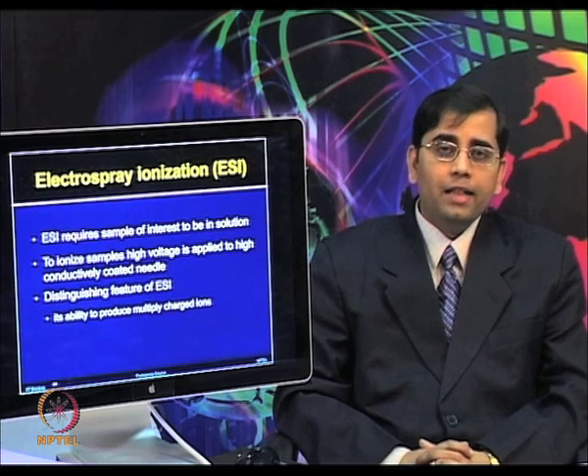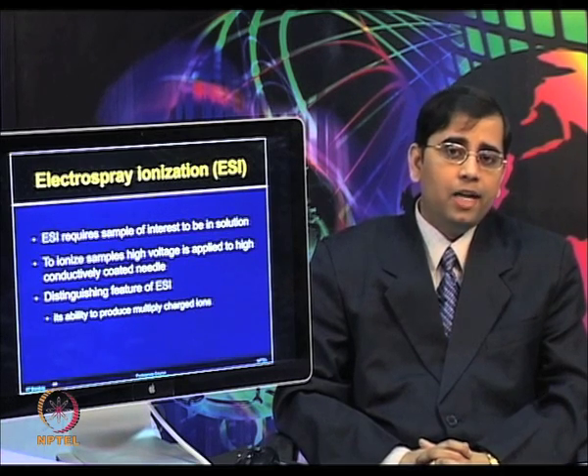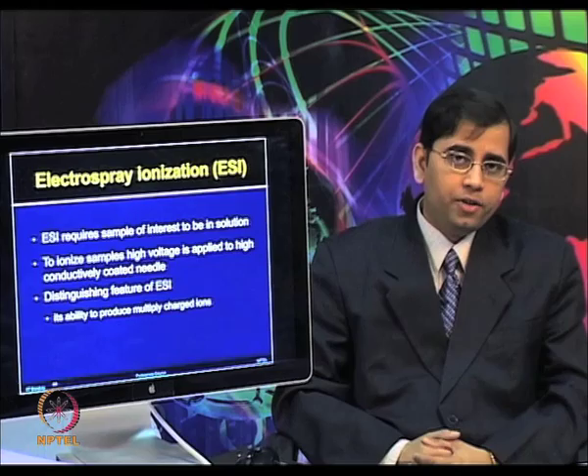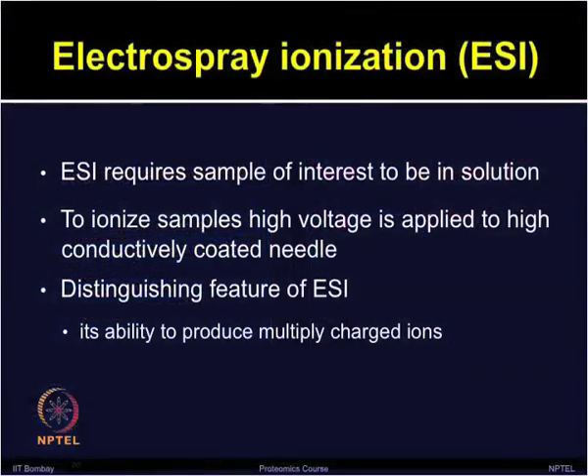ESI requires the sample of interest to be in solution, which is why we can use in-line separation with liquid chromatography. To ionize the samples, high voltage is applied to a highly conductive coated needle. This voltage results in the sample becoming charged, either positive or negative. Positive ions are primarily used for the analysis of proteins. The distinguishing feature of electrospray ionization includes its ability to produce multiple charged ions. The number of charges accepted by a particular molecule depends on its basicity and its size.